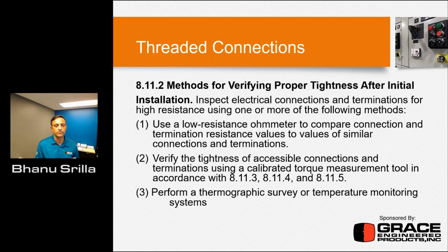I mean, thermography programs, some people do once in 6 months or once in a year. Just make sure you're documenting accurate data. And the second thing is you're comparing those on a periodic basis, meaning you do this today and you do this a year later, just go back and look at your previous measurements, check the baselines, and see what that variation should be. But if you're using a temperature monitoring device, a condition-based technique using any type of remote sensing tools, it's going to give you the trend over time automatically. Along with that, there are a lot of technologies available, and we do a few of those as well, where you can take the temperature data and combine that with current measurements, voltage or frequency dips, and then determine how this data is relevant and what kind of corrective actions have to be taken for the defect, okay?